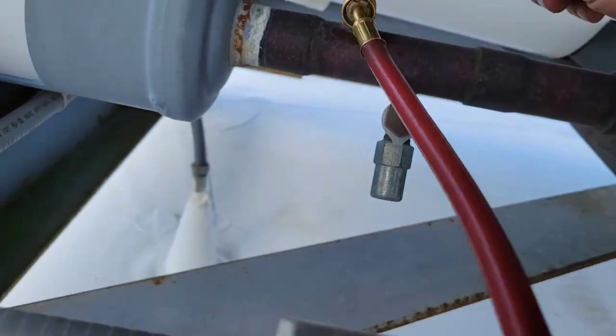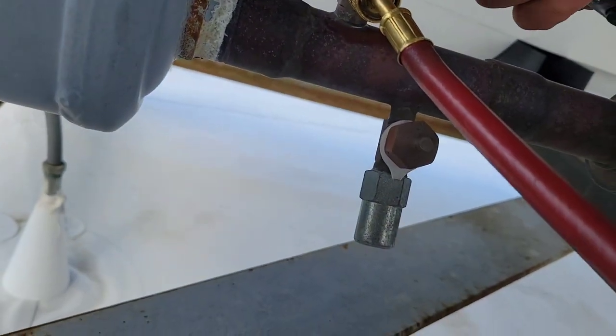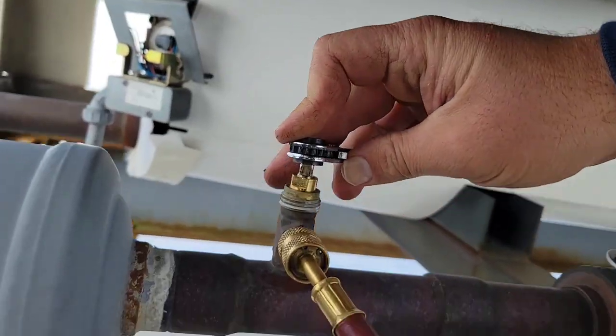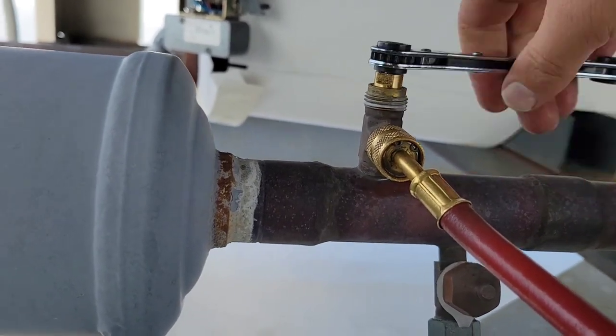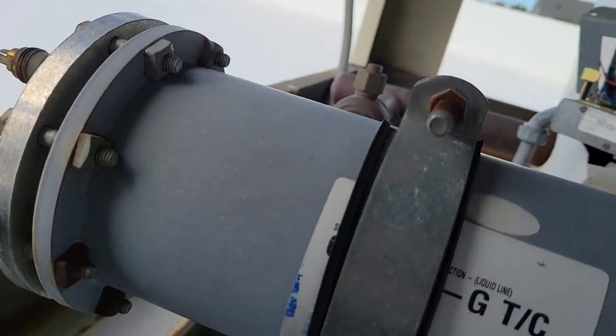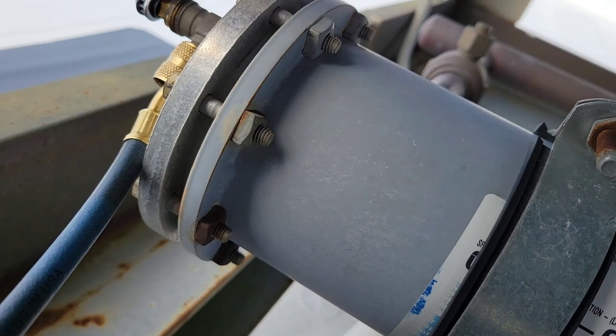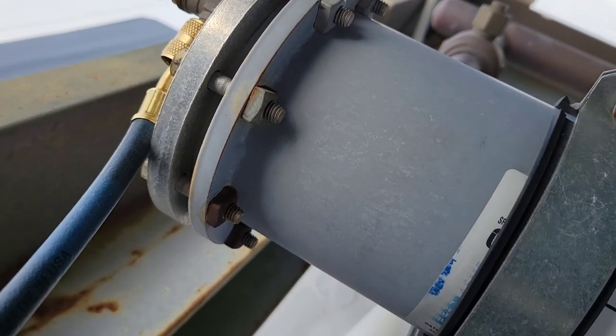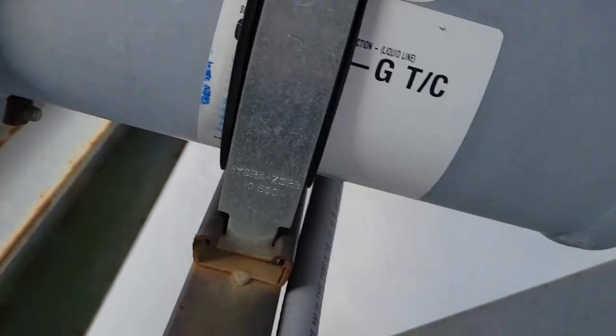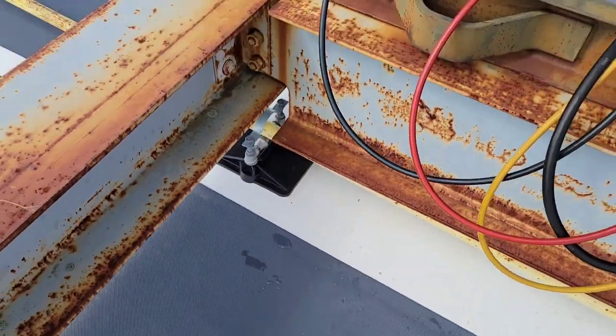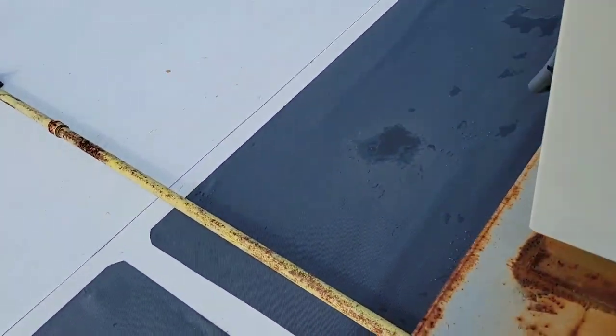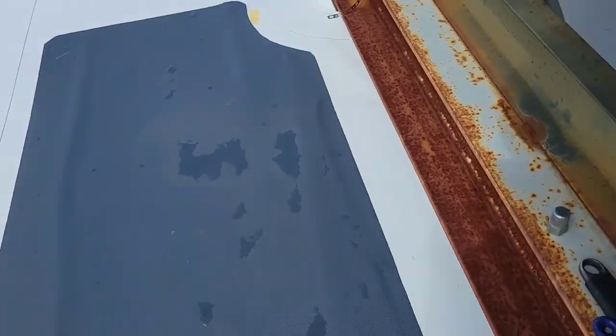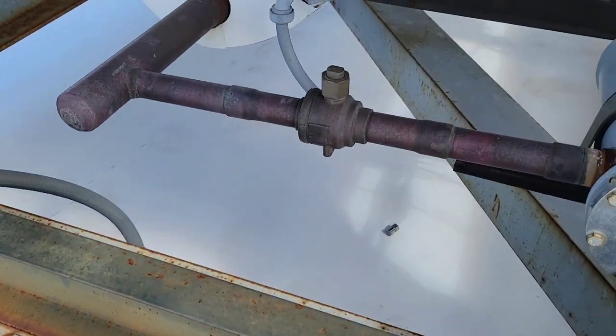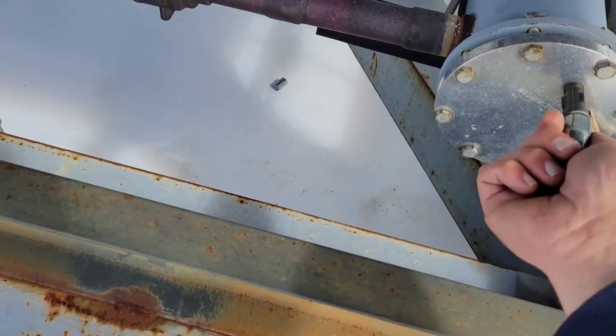Now, some of you might say, hey, if you think it's the TXV, then why are you up here doing this? Because I think it's the TXV screen, and it's because I know that this particular chain has an issue with TXV screens. The system runs warm and it creates a lot of debris that gets into the system, okay?